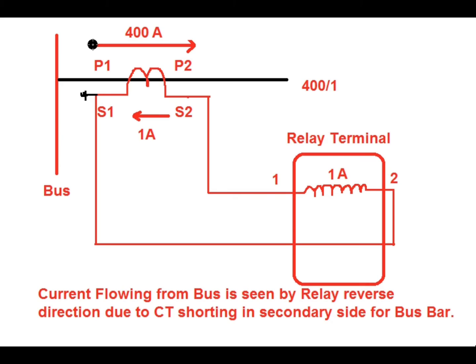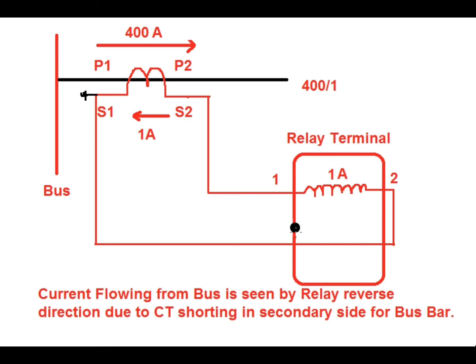Now consider current in the primary side flowing from P1 to P2 — that is, current flowing out from the bus towards the feeder. Since current flows from P1 to P2 in the primary, the CT secondary current direction will be from S2 to S1. This causes current to flow towards the relay terminal from terminal 2 to 1 direction. Since the current flows from terminal 2 to 1, the relay senses this as a reverse direction. So current flowing out from the bus is sensed by the relay as reverse direction.